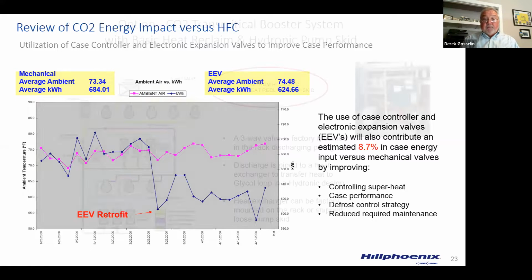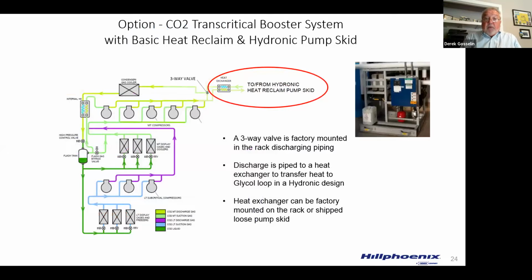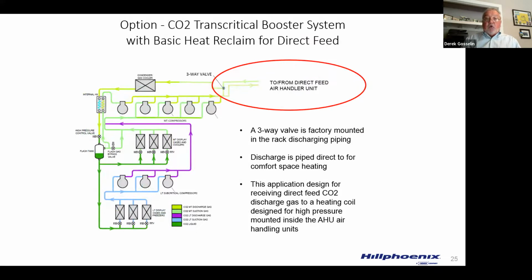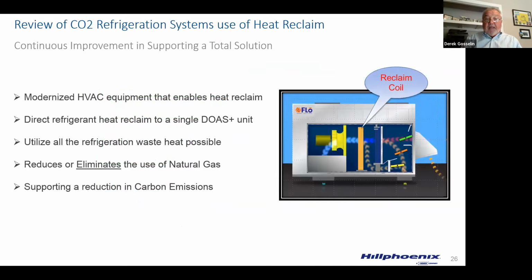Then take a look at heat reclaim. What we commonly do today in a lot of cases is go through a three-way valve, through a heat exchanger, put the heat into a hydronic pump skid, and distribute it through glycol. That's good, it works, but it's not as efficient as it needs to be. How can we take advantage of that and go direct — right to the air handler, maximizing use of the heat coming out of the CO2 system on the discharge side? It allows us to have direct equipment that uses that heat, gives us the ability to go to a single unit for heating, air conditioning, or dehumidification, and use all of the heat.